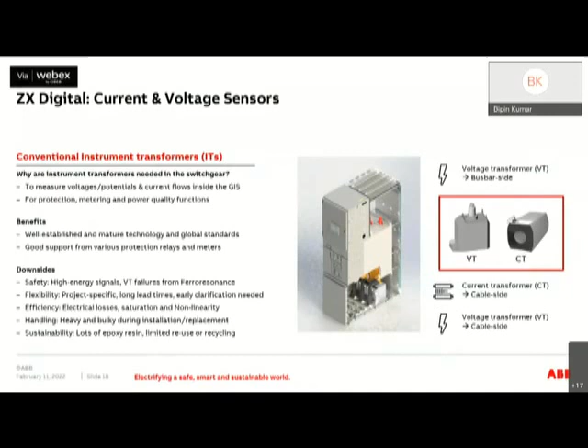What we have done here is we have a current sensor which is based on Rogowski coil principle, and then we have a voltage sensor which is based on RVD, that is resistive voltage divider principle. Now with these sensors in place, they can very well work as the conventional current and voltage transformers.